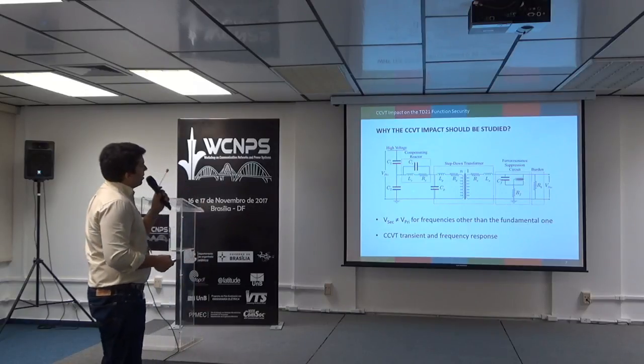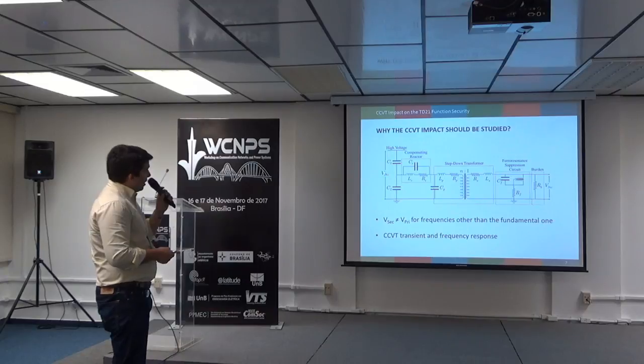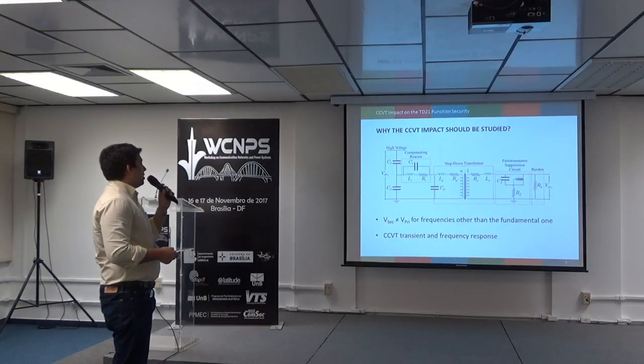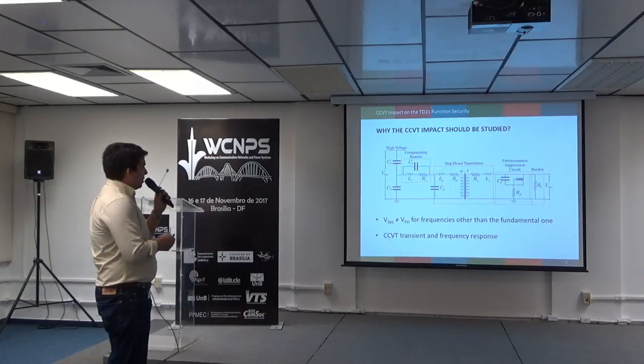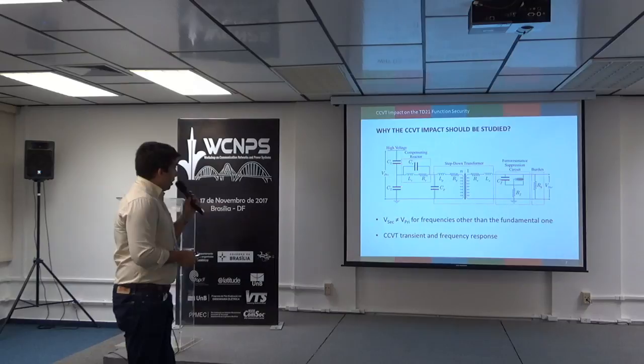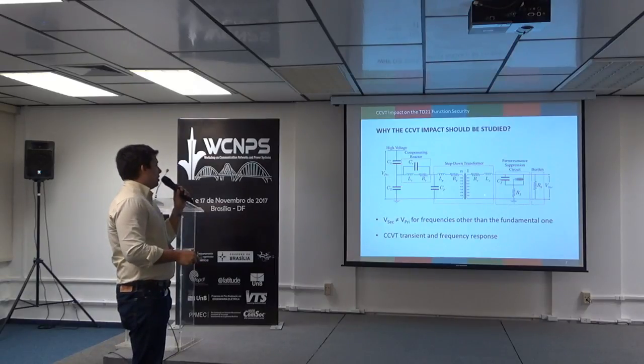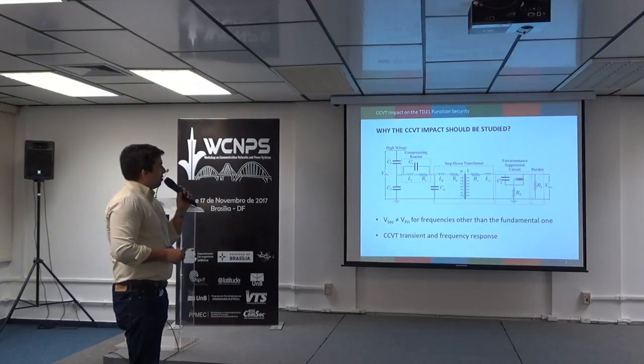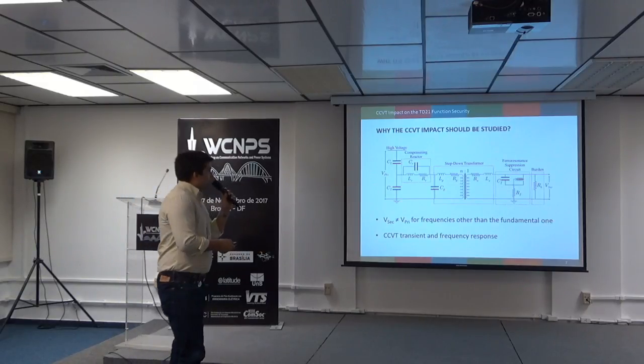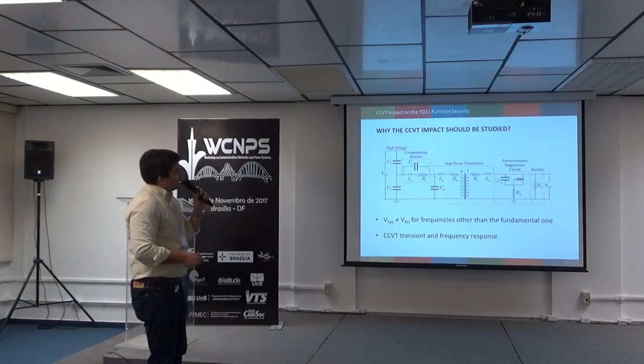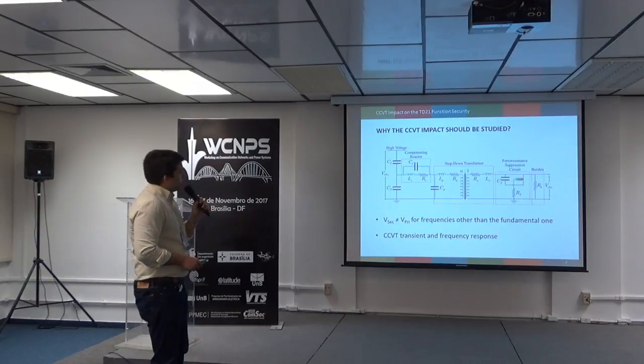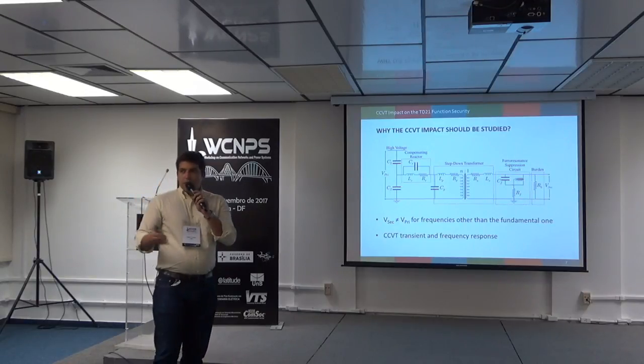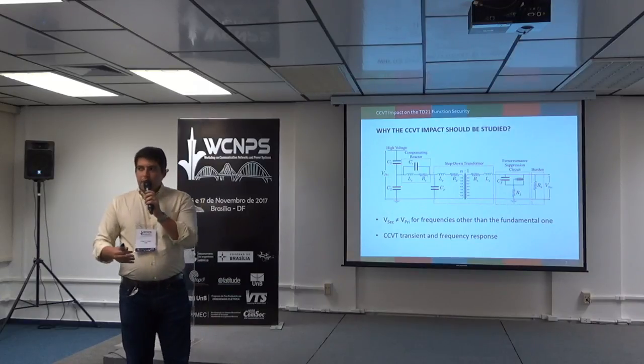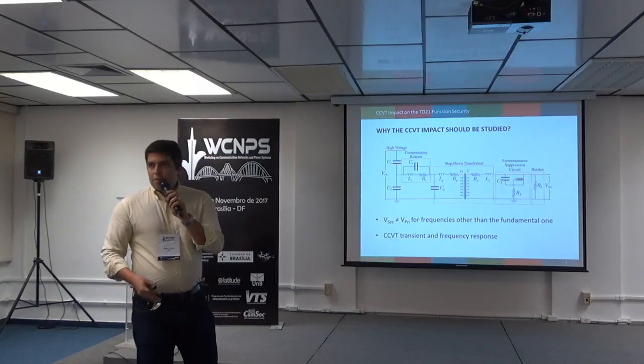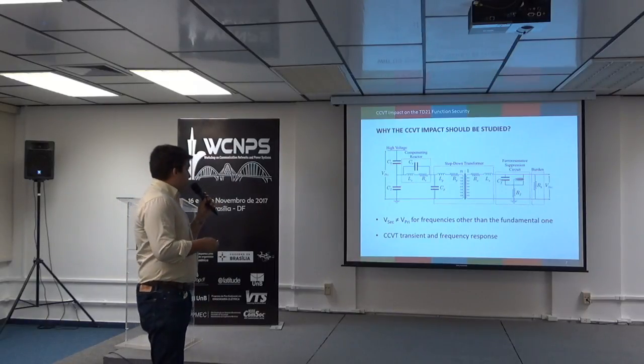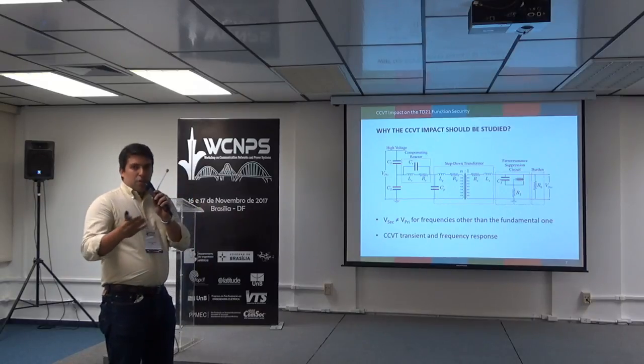Analyzing a typical CCVT circuit, we find a capacitor divider, and a compensating reactor, which is used to compensate some phase displacements between primary and secondary voltage signals. We have the step-down transformer, which is responsible for adjusting the voltage level from the primary to the secondary windings. And we have a ferroresonance suppression circuit, which is also typically used in CCVTs. So we can imagine that the secondary voltage will not be a replica of the primary voltage, because we have a lot of capacitors and a lot of inductors, so it's kind of a big filter, and we have a frequency response associated to it.